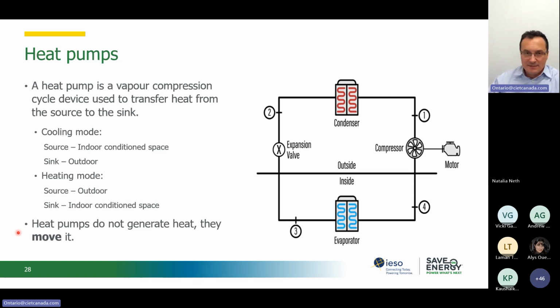And this schematic here is a very simplified schematic, showing that in a heat pump, we have four components. We have the condenser and the evaporator. These are two heat exchangers, shown like a coil. And we have a compressor and an expansion valve. So if we think about this separated through a vertical line, what we have on the compressor side, so on the right side of the schematic between the two heat exchangers would be in gas form, and what we have on the left side would be in liquid form.